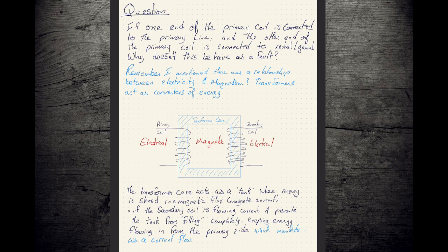But much like our water tank, if you're not taking water out of the tank, eventually the tank gets full, and then the pressure inside the tank starts to rise, and eventually the pressure inside the tank and the pressure in your supply are equal, and the water stops flowing into your tank. And the only time you get more water into your tank is if you take some out, or if your tank has a leak in it. The water will flow in to just replace what's leaving. And so we get the same thing happening in our transformers.